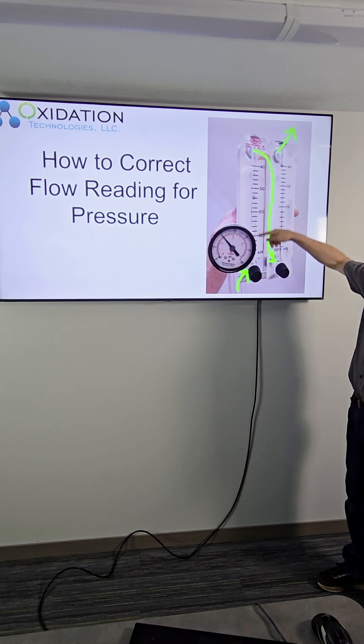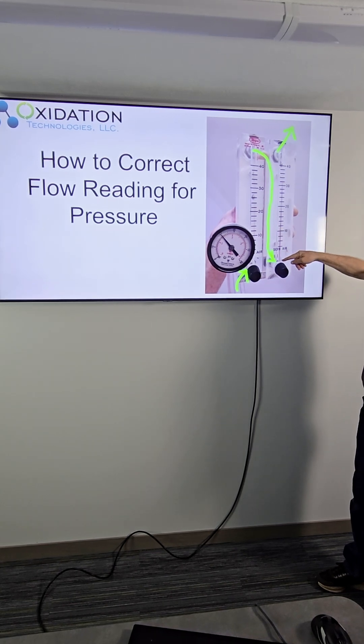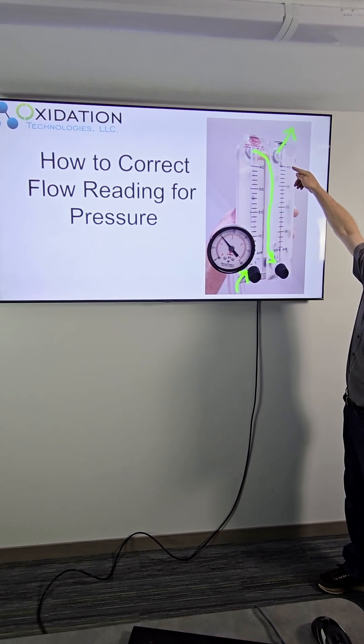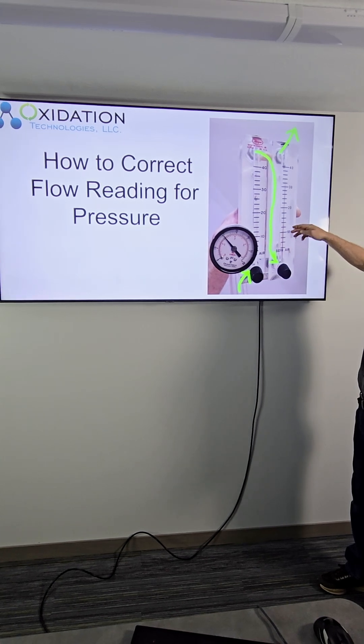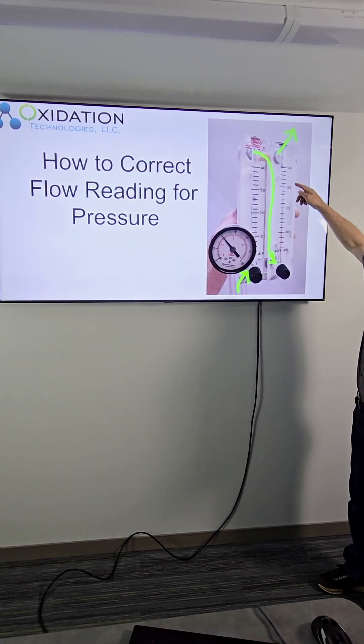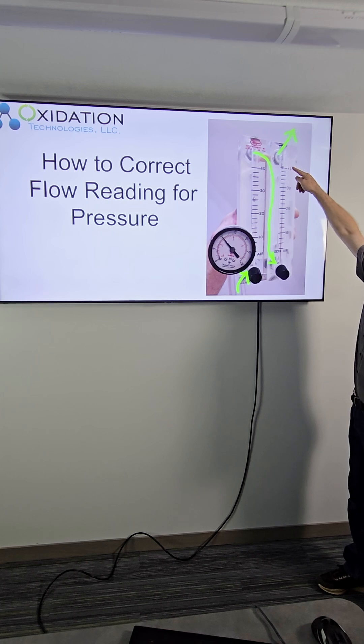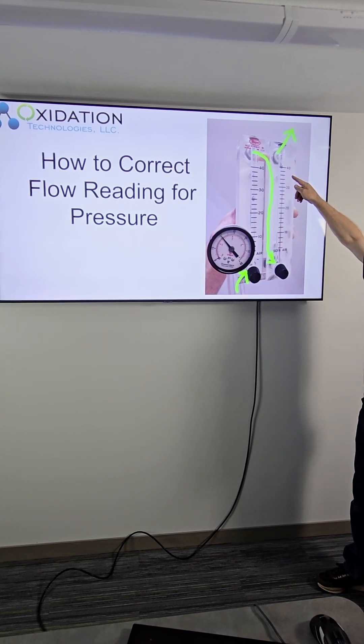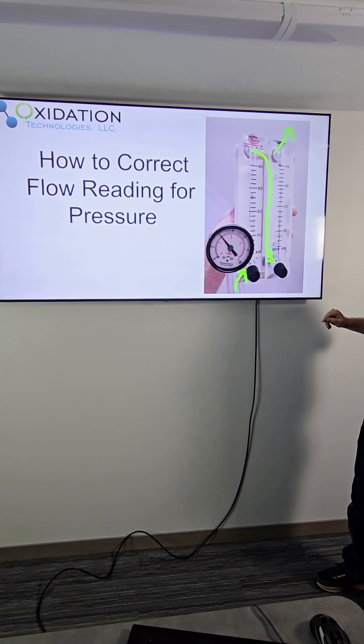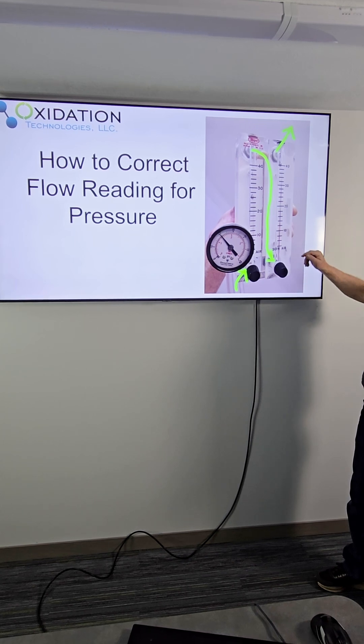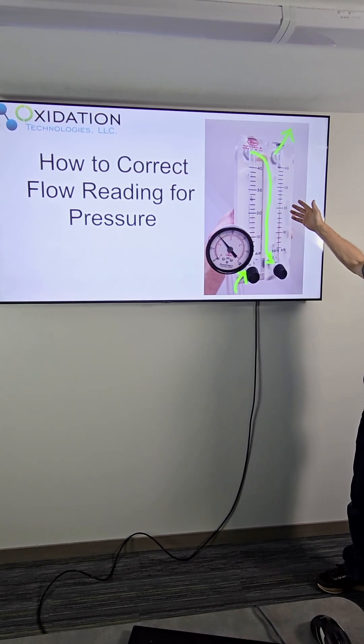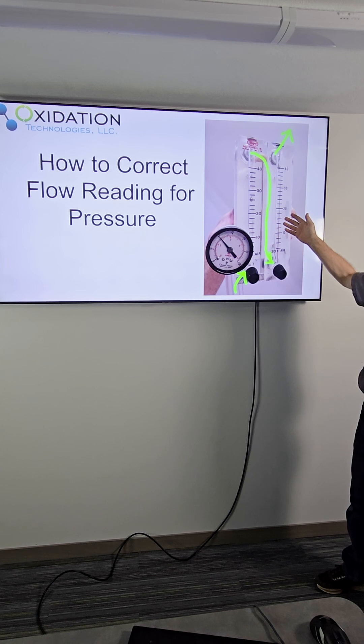So it's the same volume of gas that's flowing through both of them but you can see this flow meter that the little ball is being pushed all the way up to 40 SCFH of oxygen. And so the question is which one is correct or are they both correct?